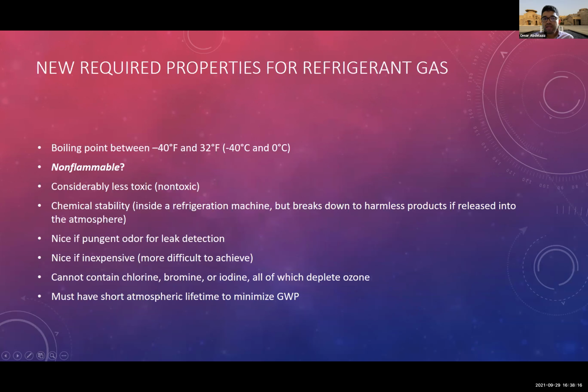All right, so what is required? What are the properties that we want to look at when we look for a refrigerant gas that meets our current challenges? The first thing, for air conditioning application, is the normal boiling point, where the refrigerant would boil at ambient pressure. We want it to be between minus 40 degrees F and 32 degrees F, or between minus 40 and 0 degrees C. We hope to be able to get it as non-flammable, because if it's non-flammable, then we don't need to worry about refrigerant or system redesign.